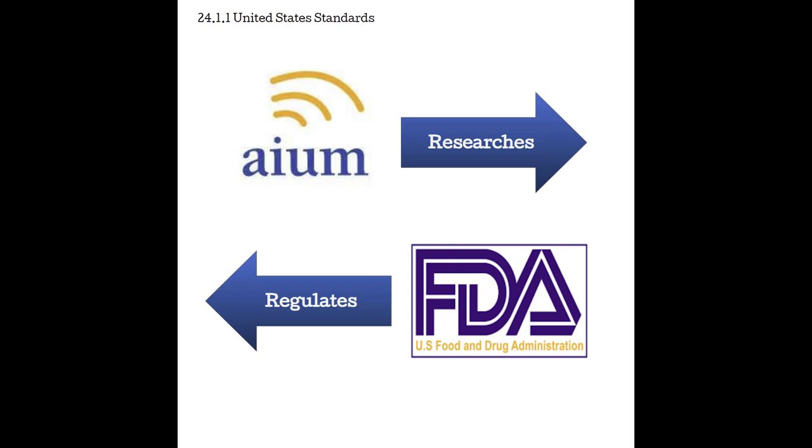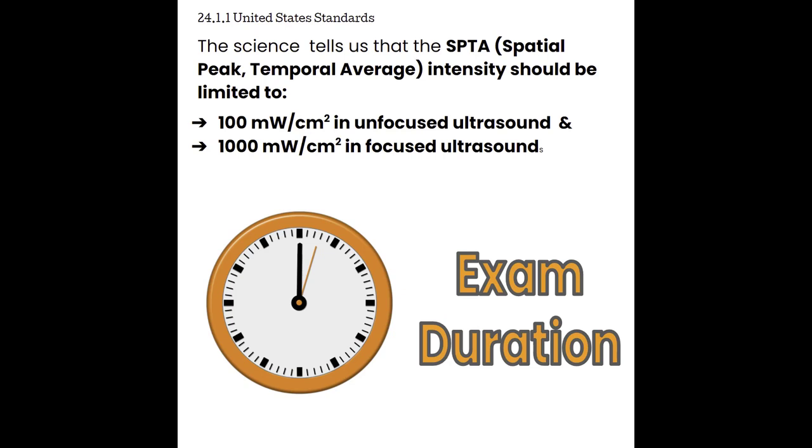The science tells us that the SPTA, which is the Spatial Peak Temporal Average Intensity, should be limited to no more than 100 mW per cm2 in an unfocused ultrasound, and 1000 mW per cm2 in focused ultrasound. The science also highlights that it's actually the exposure time, or the exam duration, that increases the risk of adverse effects for the patient the most.